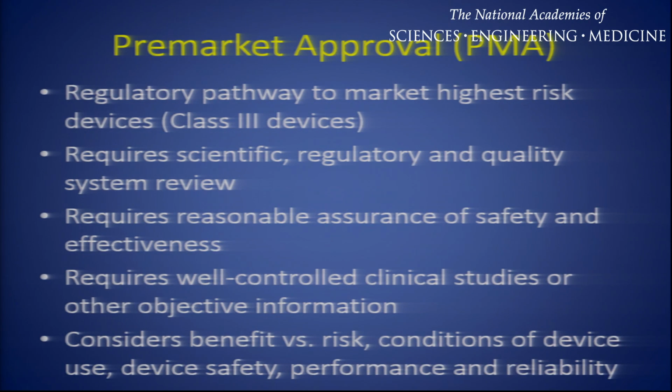Pre-market approval. Remember, these are the highest risk devices. It's called the PMA program. It requires scientific, regulatory, and quality systems review of the sponsor's organization, or the company that's making the device. It requires a reasonable assurance of safety and effectiveness. Well-controlled clinical studies or other objective information is usually part of this review process, and it considers the benefits versus the risk, conditions of device use, device safety, and its performance and reliability.